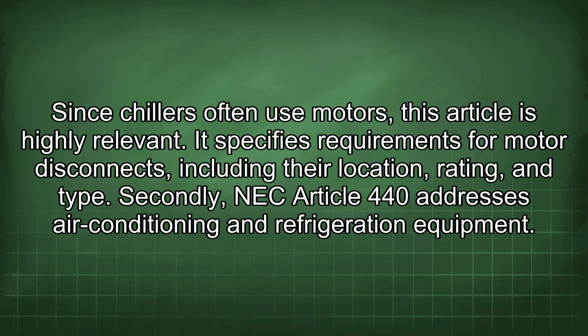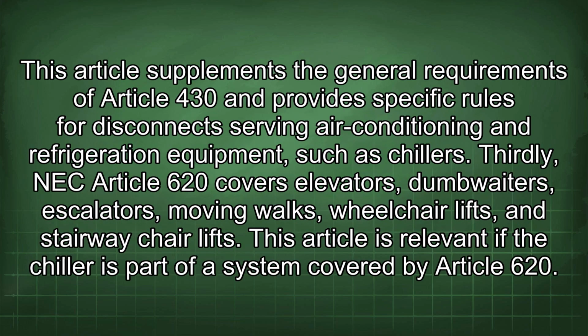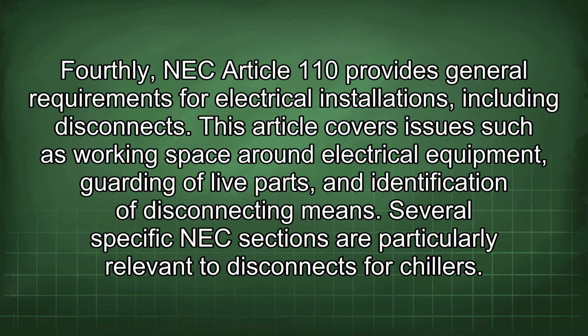It specifies requirements for motor disconnects, including their location, rating, and type. Secondly, NEC Article 440 addresses air conditioning and refrigeration equipment. This article supplements the general requirements of Article 430 and provides specific rules for disconnects serving air conditioning and refrigeration equipment, such as chillers. Thirdly, NEC Article 620 covers elevators, dumbwaiters, escalators, moving walks, wheelchair lifts, and stairway-chair lifts. This article is relevant if the chiller is part of a system covered by Article 620. Fourthly, NEC Article 110 provides general requirements for electrical installations, including disconnect. This article covers issues such as working space around electrical equipment, guarding of live parts, and identification of disconnecting means.